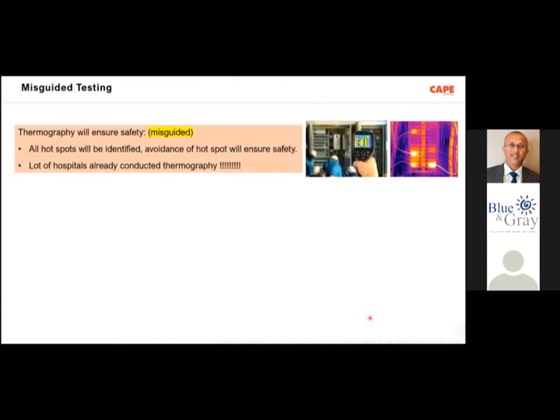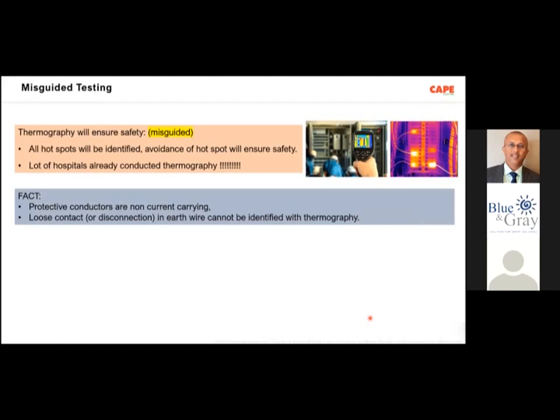A misguided test: in Bombay, in a lot of high-rise buildings, I've seen people doing thermography in order to find out a loose contact in a conduit. You have a copper wire, 2.5 square mm or 1.5 square mm, inside a conduit, and thermography has been done to find a loose contact in that conduit, which is absolutely wrong. This is not the correct way. So you should do it in the proper way.